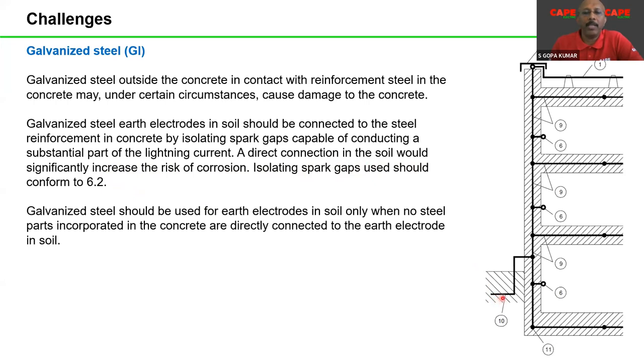So for example, what it says is, if you wanted to connect, you have a natural component used as a down conductor and you have to connect it to something which is in soil and that something is galvanized. Don't connect directly is the recommendation. You put a spark gap in between. So electrical isolation or a spark gap is necessary. So these recommendations are there for soil.